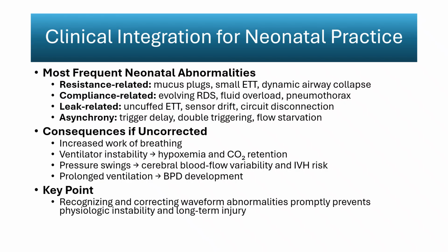Uncuffed tubes, sensor drift, and loose circuit connections cause inspiratory and expiratory limbs to separate, reduce measured tidal volume, and impair trigger detection. Finally, asynchrony remains a major contributor to instability. Trigger delay, double triggering, and flow starvation all arise when the ventilator's timing or flow delivery does not align with the infant's neural effort. If these abnormalities go uncorrected, the consequences are significant.